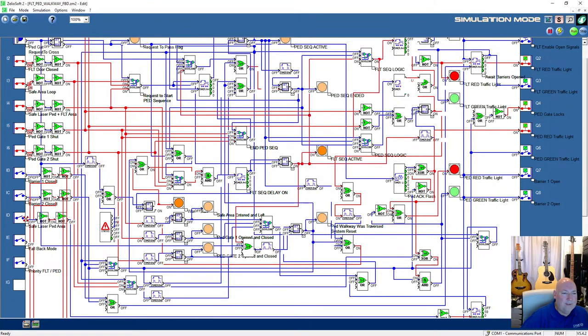Right, so I'd have to just shut the barriers myself for the safe laser. So they're on. And it's transferred over because I have shut. They've opened and I'm okay. So then I initiate a ped call. And it should time out and switch over to ped. And I would have to manually, stays as it is, yeah. I'd have to manually shut these two for it to, oh, it's actually switched over and it's counting, yeah, that's right. Okay. Now, I might have my inverter timers the wrong way around. Oh, my timers on, delay off, round the wrong way around.